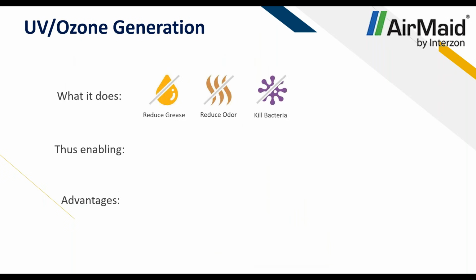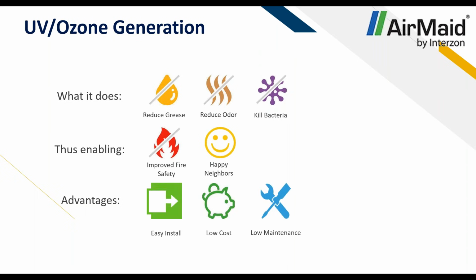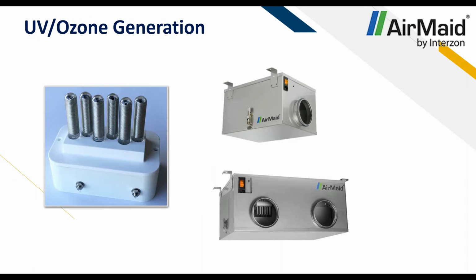So what it does is reduce the grease, which reduces odor as well as kills bacteria, thus enabling improved fire safety and happy neighbors with those mitigated smells, especially. And it's very easily installed, low cost, and low maintenance. So we're going to get more into this. Here's just some more pictures of what these units look like with their ozone generators, their cells. You can see them inside the duct there.